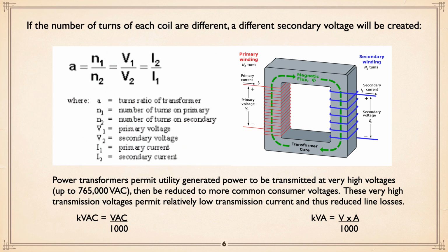Taking that a step further, you have the formula that the number of turns, primary and secondary, N1 and N2, will give you the voltages, V1 and V2, and the reverse, because of Faraday's law, current flow varies inversely. For example, let's pretend we're going from, pick a number, let's say 25,000 volt, and we want to bring it down to 600 volt. So you'd have an appropriate number of turns on the primary side and a smaller number of turns, quite a bit smaller, 25,000 divided by 600, on the secondary side. So all the turns on the primary create a magnetic flux. That in turn on the other side, as that magnetic field goes through the conductor, creates a secondary voltage in proportion to the number of turns.